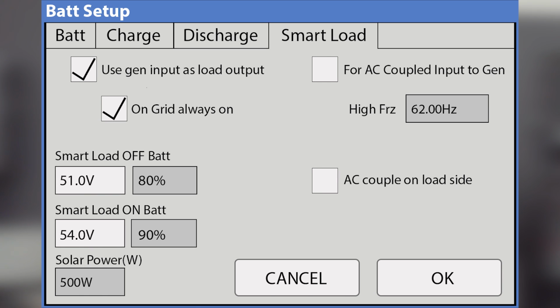Gotcha, so you can set these different triggers here. If you're using it as a load output, your smart load on value would need to be the high one, and the smart load off value would be the low one. In this case, we'd continue to power the loads with the default settings until the battery got to 80%, and then we'd shed the loads on the gen breaker to prioritize whatever's on the load breaker if the grid's out.